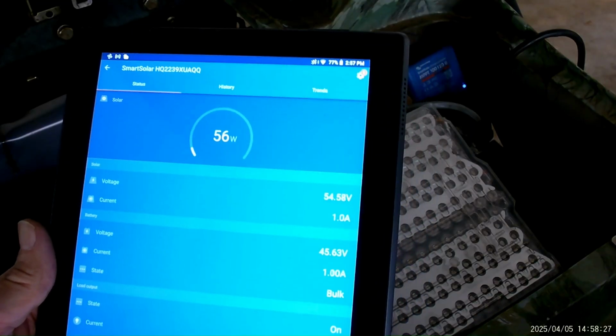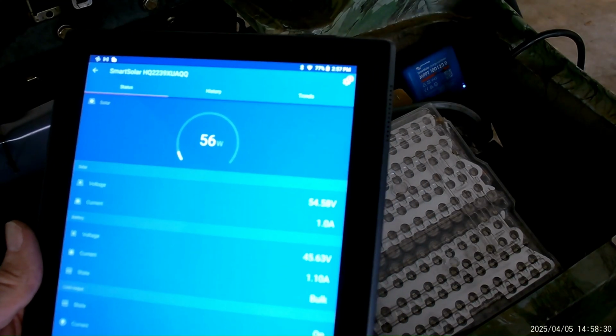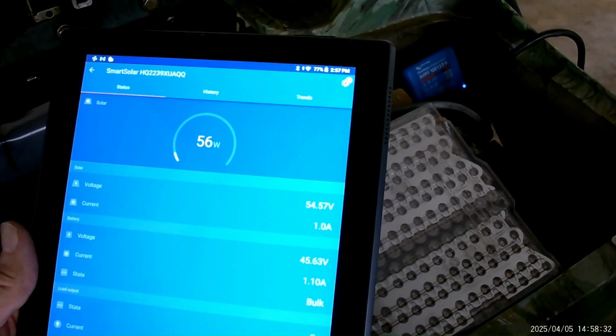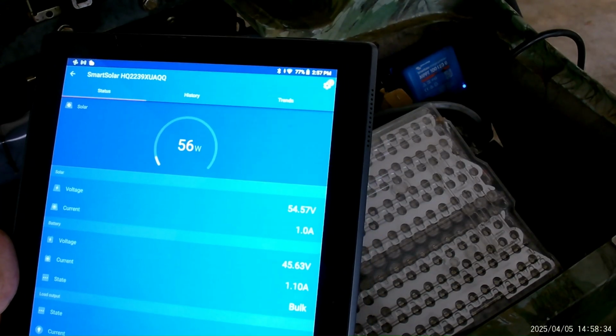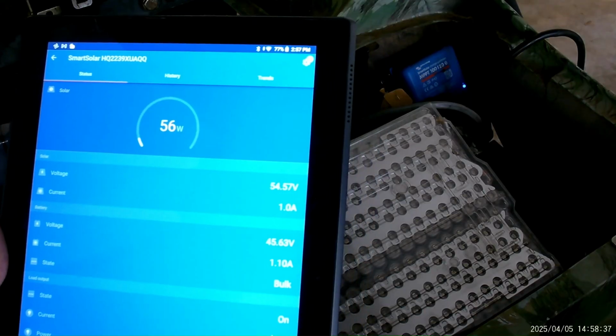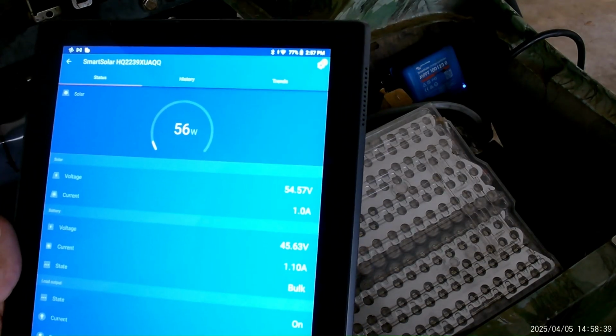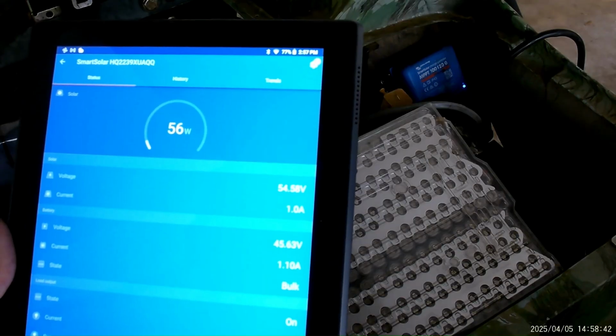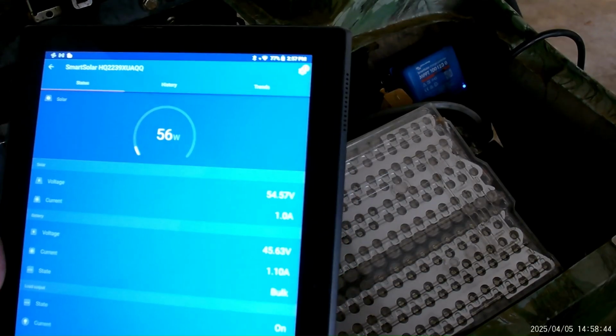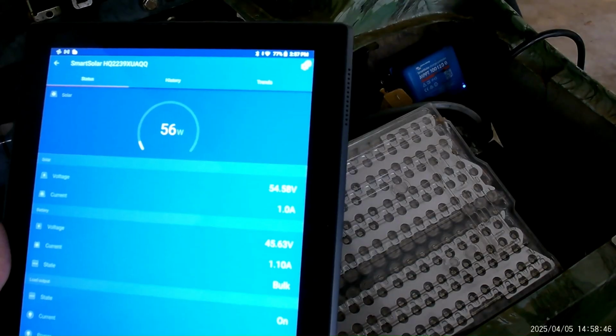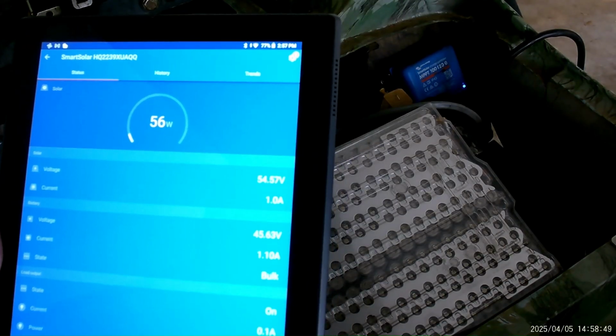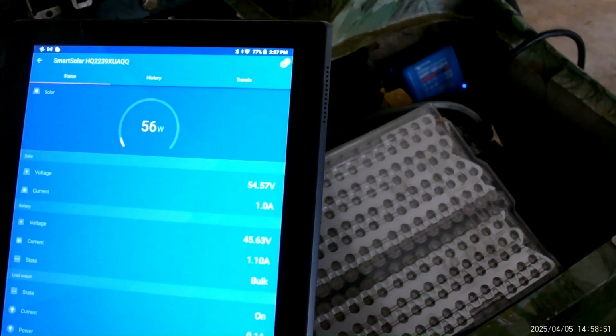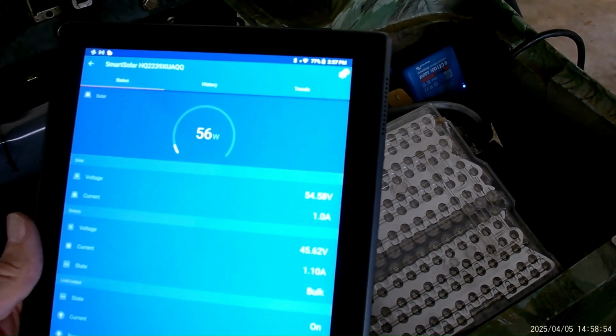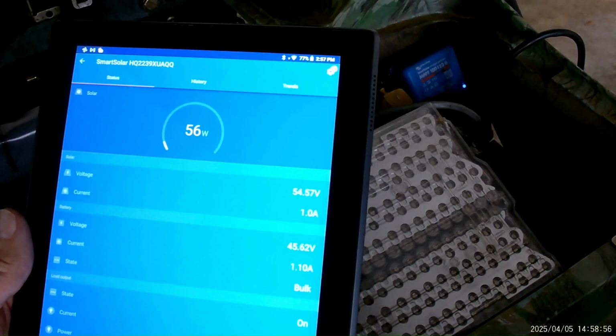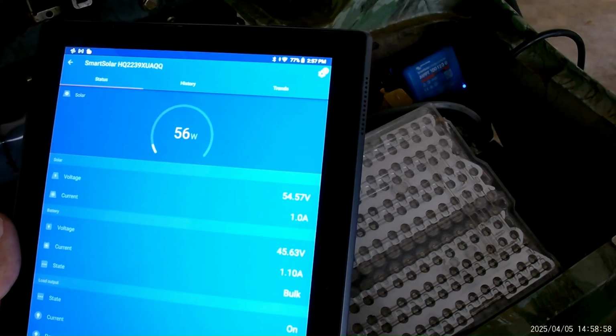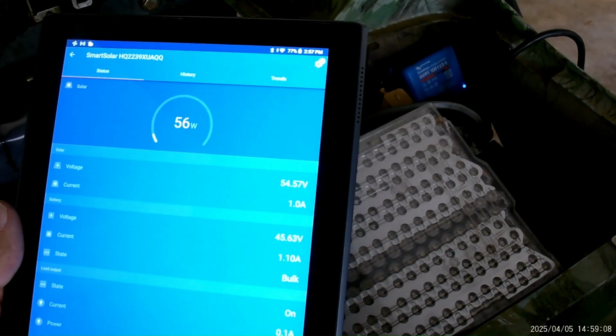It's charging with a whopping 56 watts, but you can see it's showing the input voltage to the charge controller is 55 volts, and the output is 45.63. That's the battery's voltage right now, at 1.1 amps of charge. Now, why, you might ask, why is the input 1.0 amps, but the output is 1.1? That's because this is an MPPT controller, maximum power point, and it basically has an inverter in it, push more current into the battery.